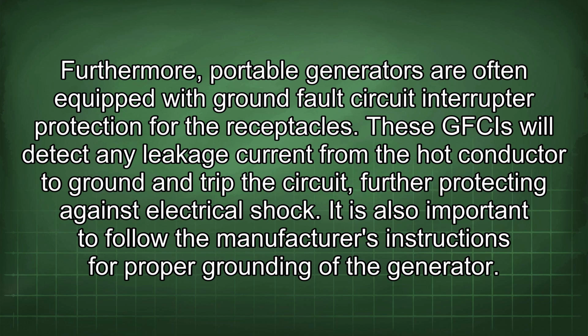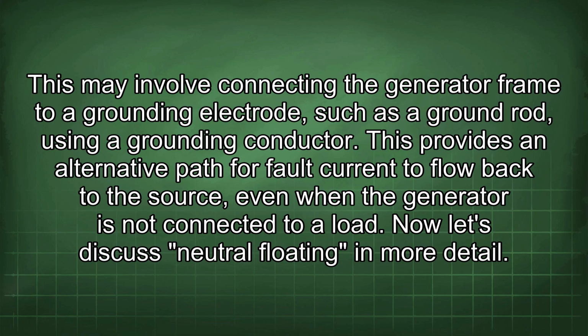It is also important to follow the manufacturer's instructions for proper grounding of the generator. This may involve connecting the generator frame to a grounding electrode, such as a ground rod, using a grounding conductor. This provides an alternative path for fault current to flow back to the source, even when the generator is not connected to a load. Now let's discuss neutral floating in more detail.